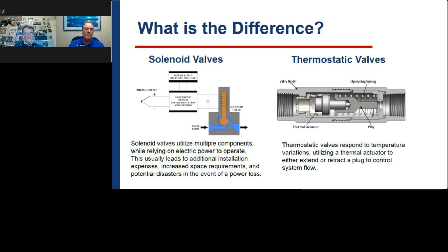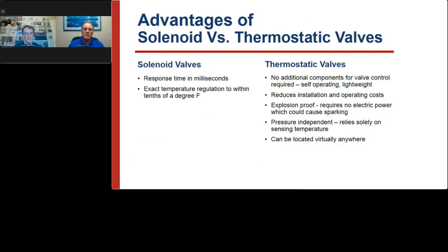So from that, the advantage of solenoid valves versus thermostatic valves, hands down, is the response time, which is in milliseconds. And also, exact temperature regulation to within tenths of a degree F is totally possible with that.